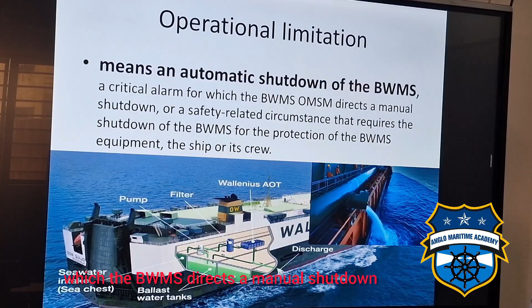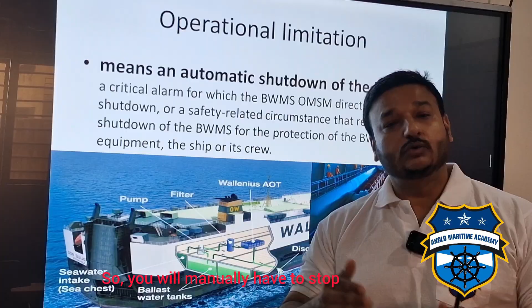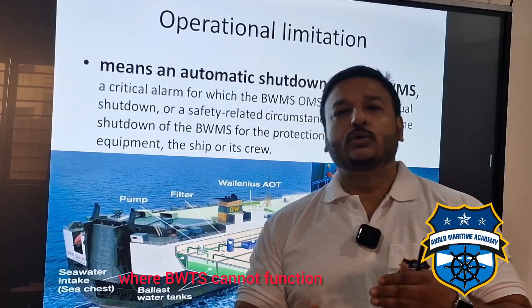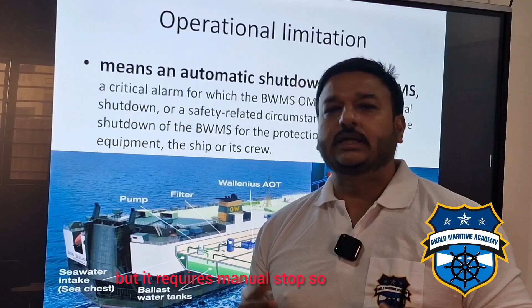So there is an alarm. Now a lot of mud has come in, the filter is choked, the sensors have given way. There will definitely be some alarm in your BWTS. BWTS monitoring systems will give you certain alarms, and it will require your BWTS to stop. So you will manually have to stop, or it will trip by itself because the water flow has reduced to a level where BWTS cannot function. Now all the sensors are giving alarm, so your BWTS will eventually trip, but it requires a manual stop. So that is what your operational limitation says.